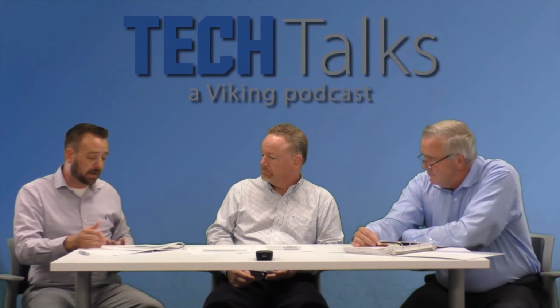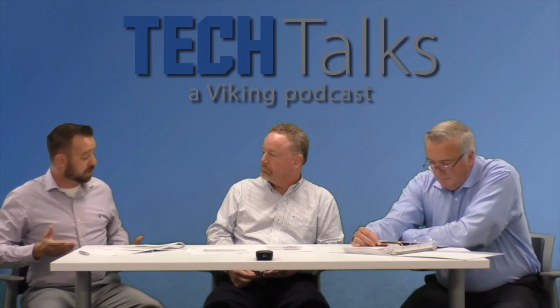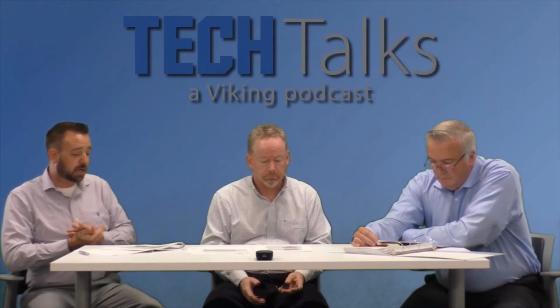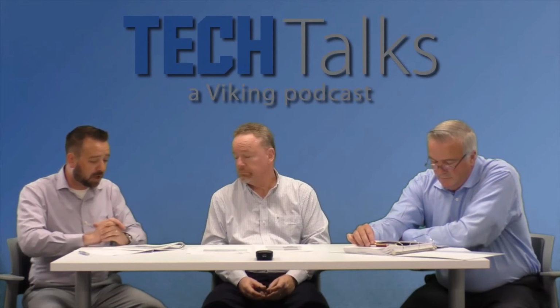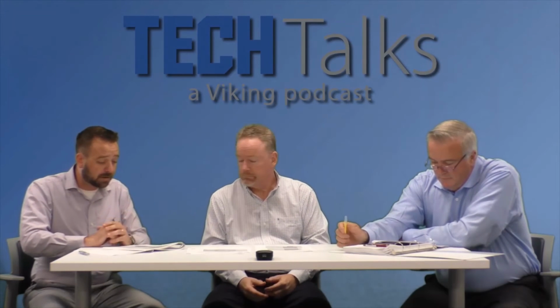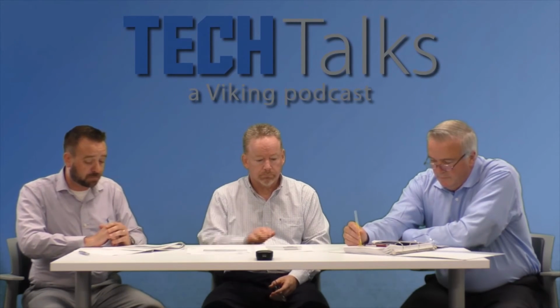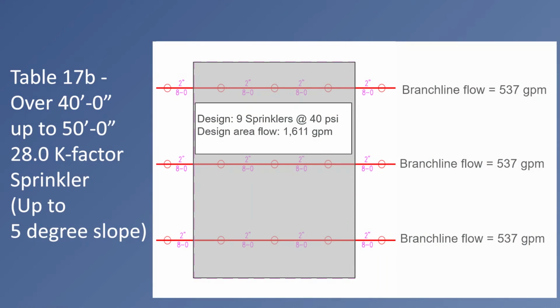So based upon the 9 sprinkler design at 40 PSI, using the K28 sprinkler, if we look at figure 1, we'll see that we were able to get down to 2-inch branch lines in that situation. But it's even a little bit more significant than that, because not only were we able to get down to 2-inch branch lines, but we also had 2-inch riser nipples. We had a 4-inch primary main and a 4-inch secondary main.